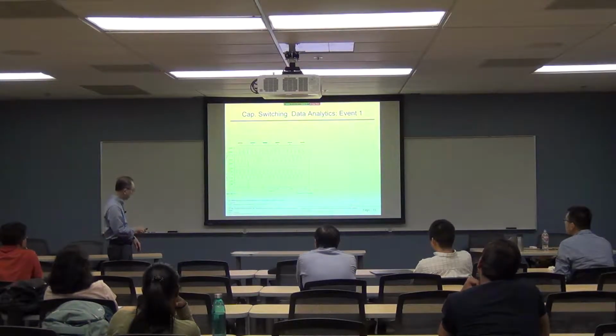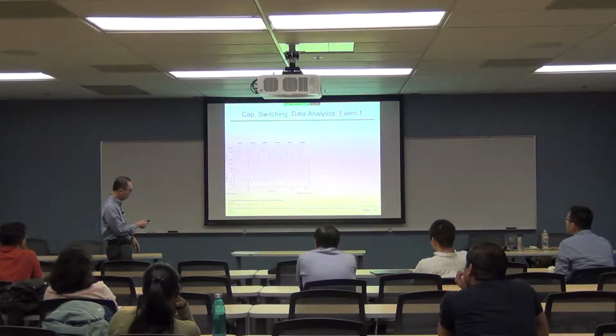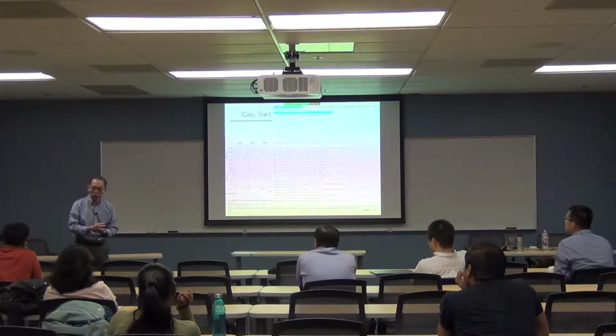You don't see any restrike conditions. Therefore, the circuit switcher declares that there are no restrikes during closing in any phase. Because this is a closing event, it will tell you whether during closing there is a pre-strike or not, because sometimes when the switch is closing like this - most of these are electromechanical switches.